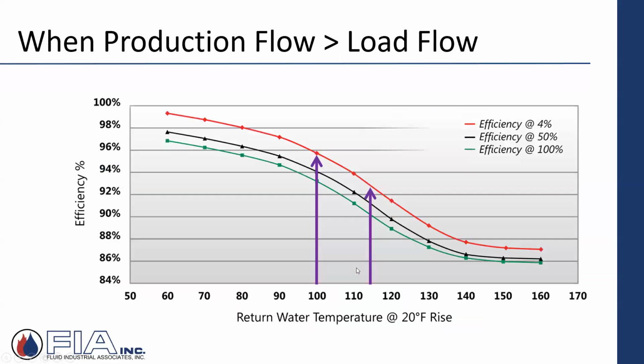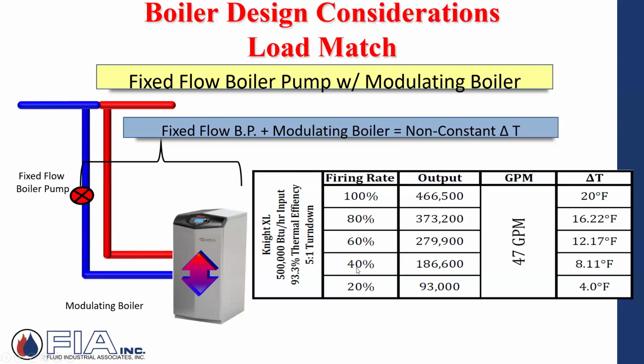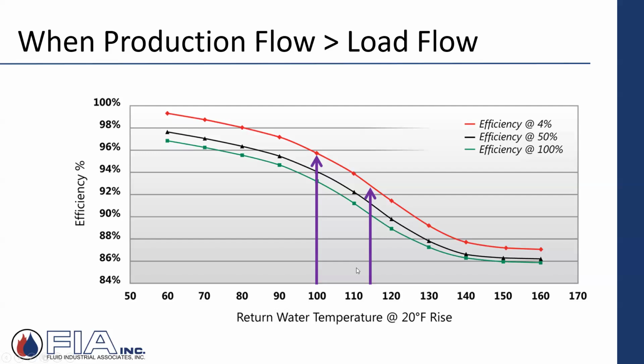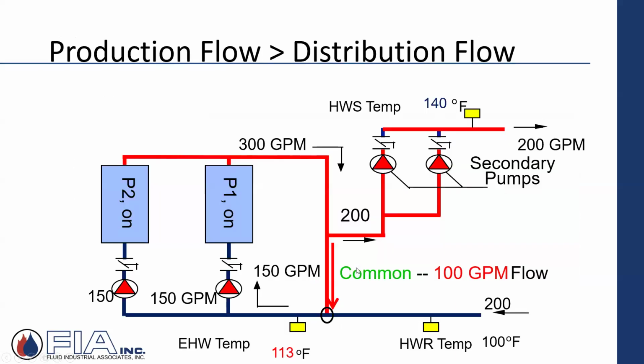So I just want to jump to a real quick. Here's the issue. When you're into high efficiency, condensing, modulating boilers, one of the things that can really impact that efficiency point is the return water temperature, right? And if you ever have a scenario where in my boiler plant I'm taking some hot boiler water and I'm actually not sending it out to the system, but I'm bringing it back into the return, that can happen when I do fixed speed boiler pumps instead of variable speed.